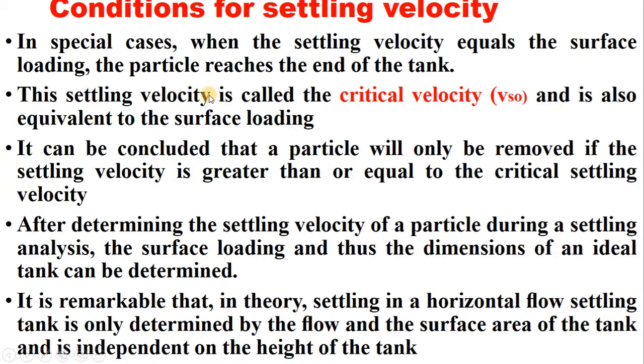This settling velocity is called the critical velocity, Vs naught, and is also equivalent to the surface loading. It can be concluded that a particle will only be removed if the settling velocity is greater than or equal to the critical settling velocity.